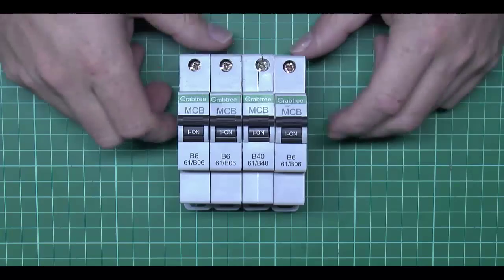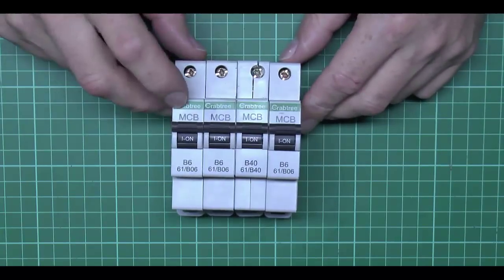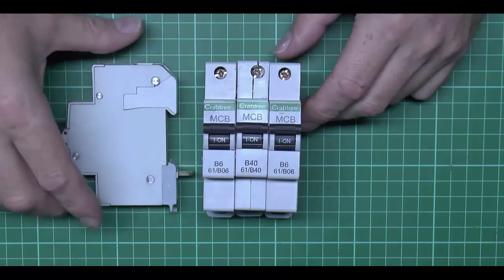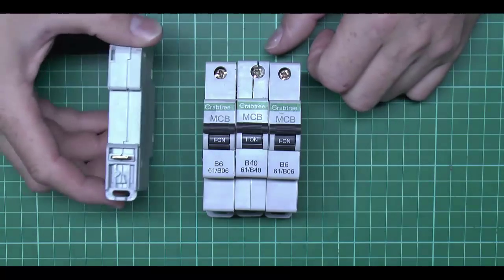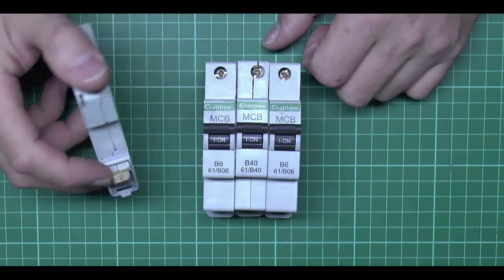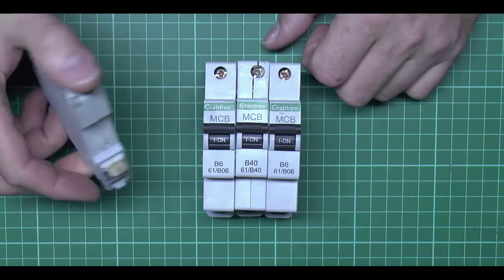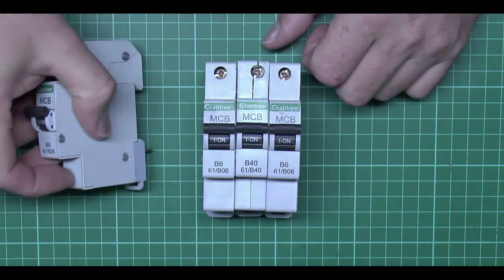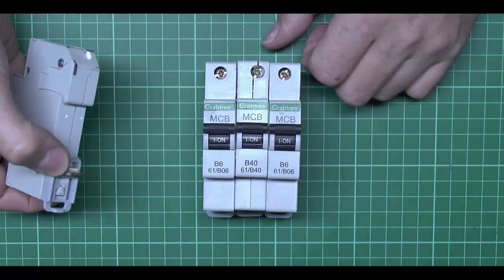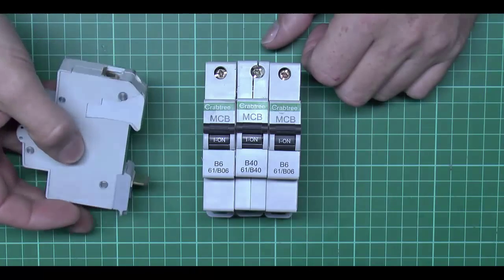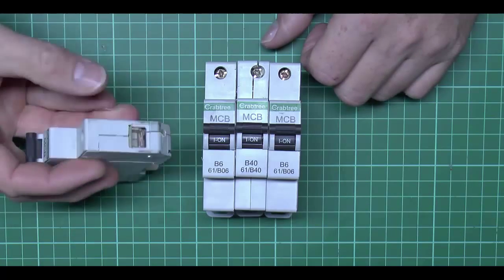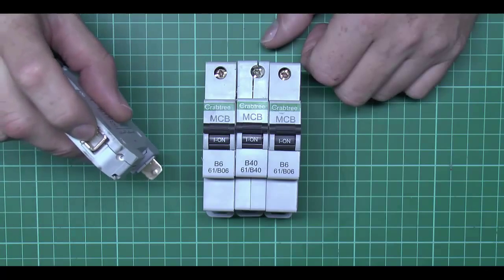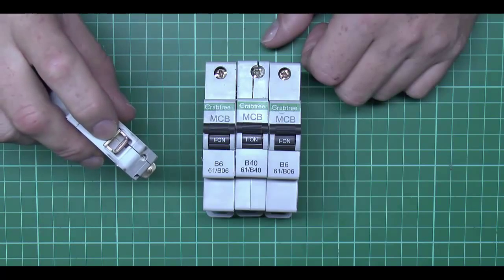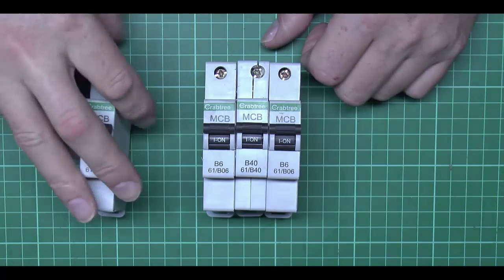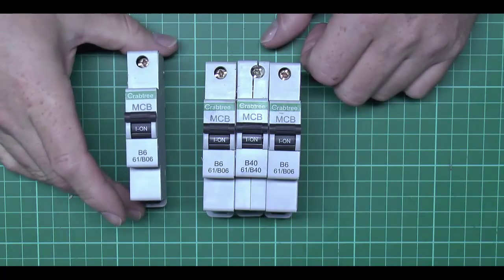Now, these are fairly ordinary circuit breakers, so these are Crabtree branded, but again, they're all going to be pretty much the same design. And these ones have the plug-in arrangement on the back. Most of the others actually have a screw terminal at the bottom. These just have that sort of pre-made piece which plugs into the corresponding part in the consumer unit. And they've got the usual terminal on the top there for the wires going to the circuit. And these are just single pole devices.